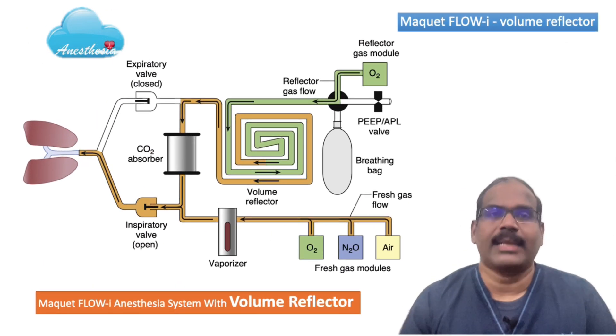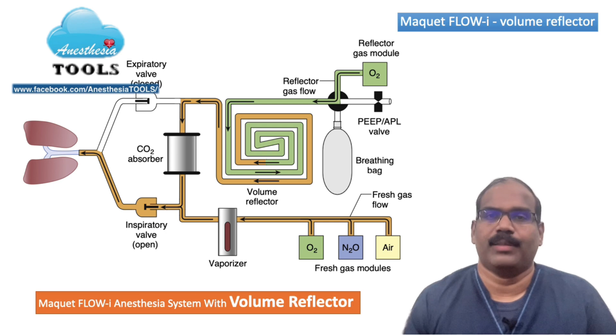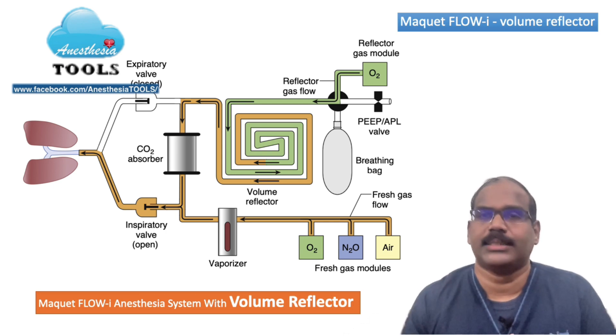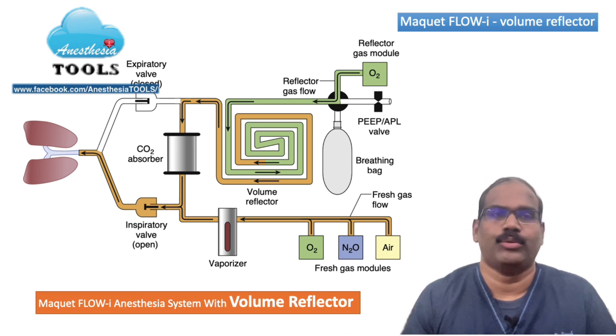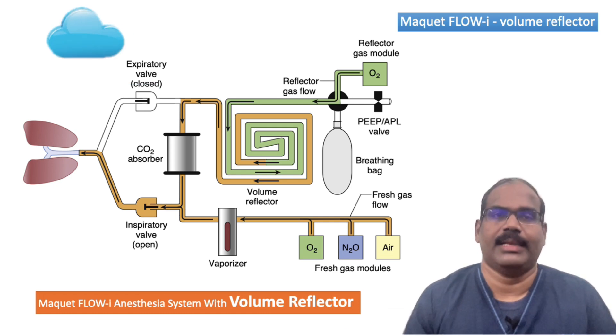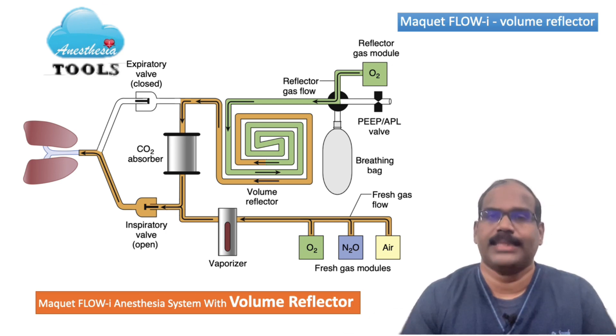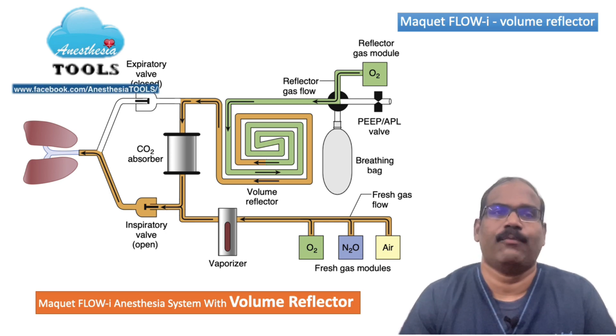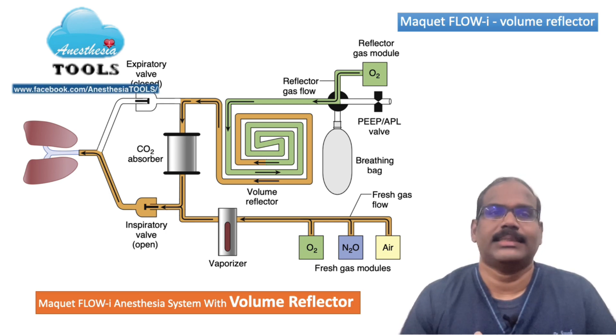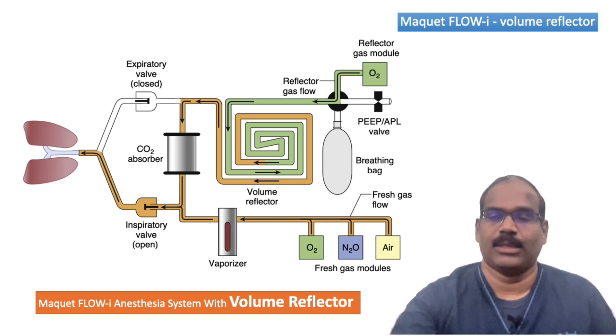The Maquet FLOW-i anesthesia ventilation uses a novel device called the volume reflector to act as the reservoir. The volume reflector is essentially a long plastic tube with a volume of 1.2 liters, coiled compactly to fit in the anesthesia workstation. It is functional and in circuit during all modes of ventilation, acting as a volume reservoir while simultaneously preventing mixing between the gas at the two ends of the tube.